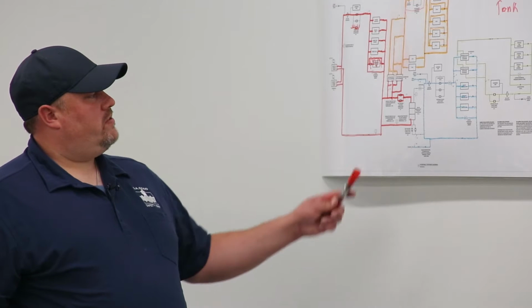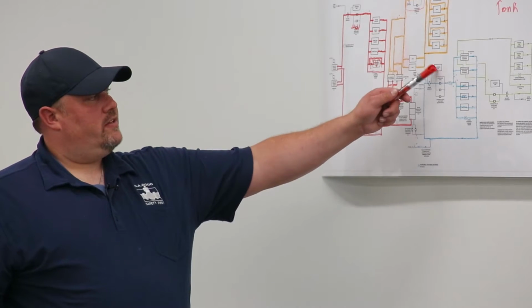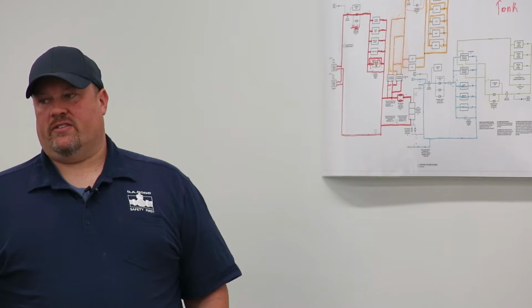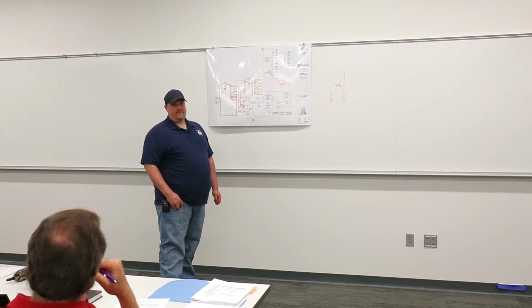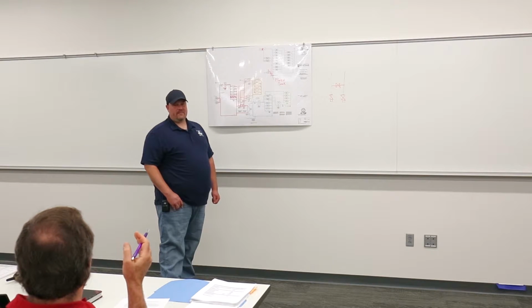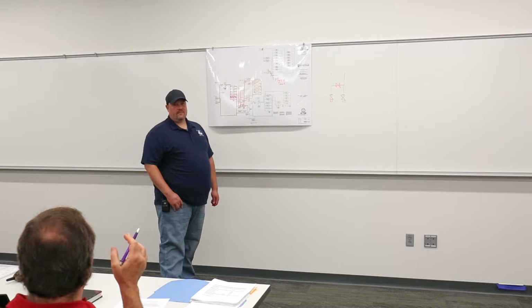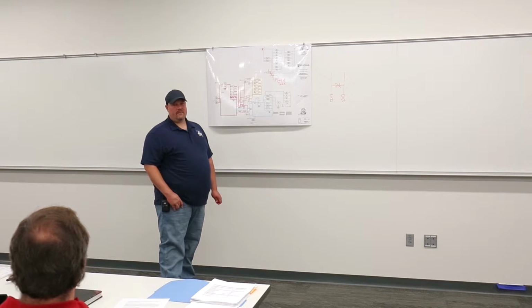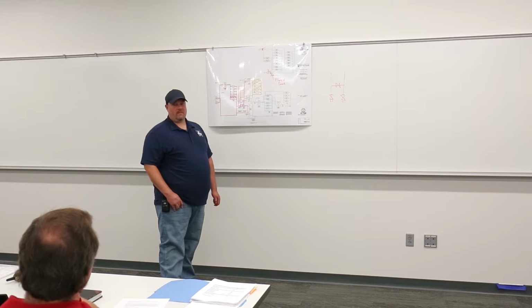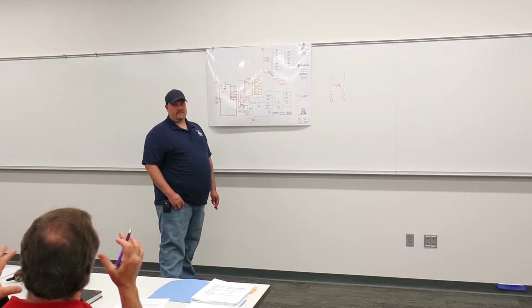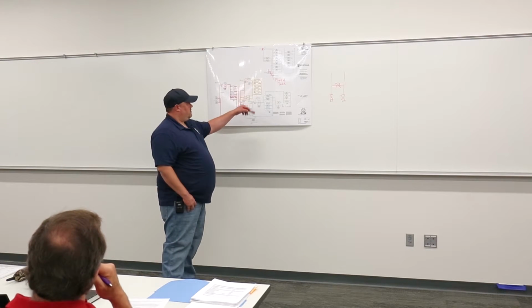We do have valves and drains on the expansion tanks. When we put a valve in, they say not to, I always put a valve in and take the handle off. You never know when that thing's got to be serviced, and it's just a smart thing to do. In that case, we might just shut it off. Yes, sir. And just have it there. In the event that they had to drain the plant system, they could open it and it would stay on its own.